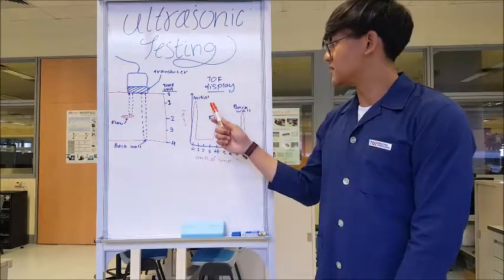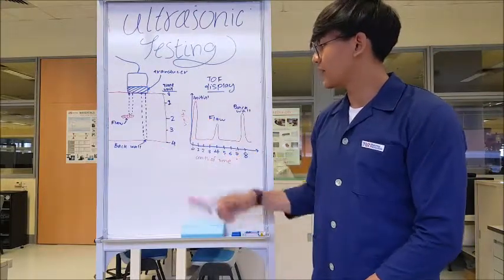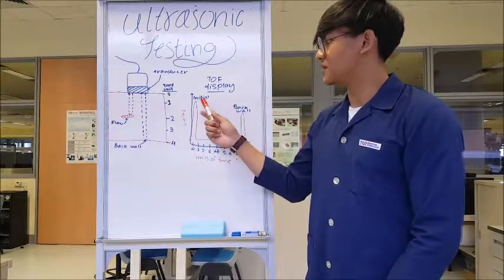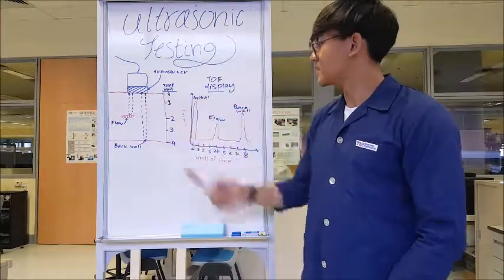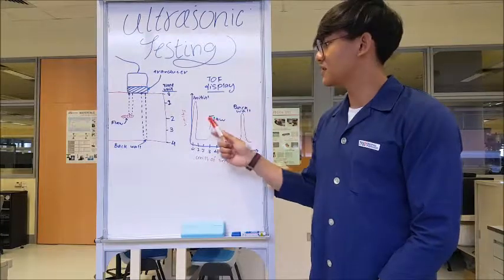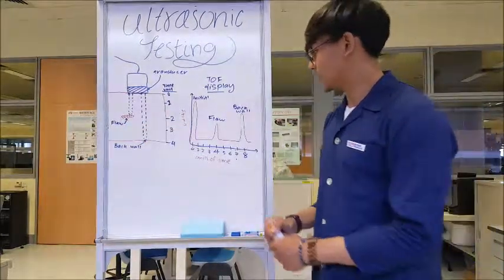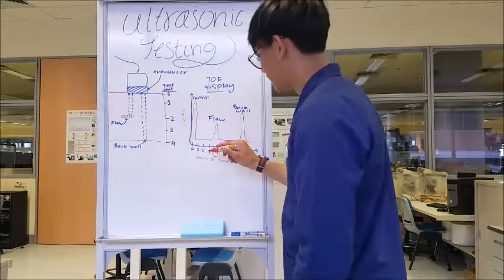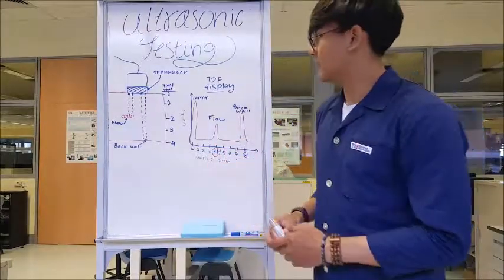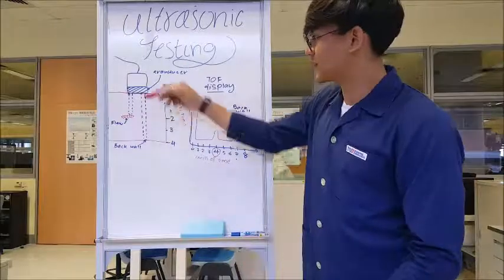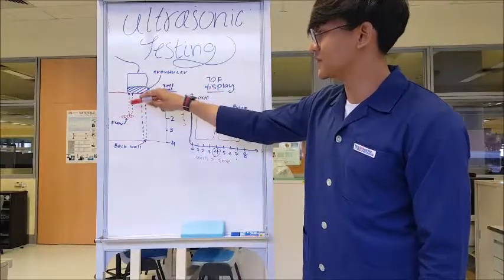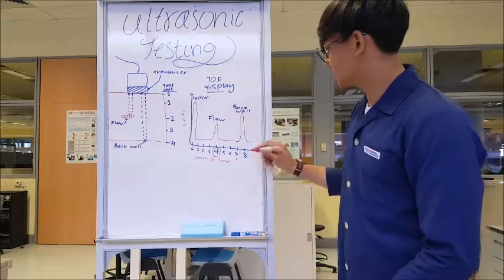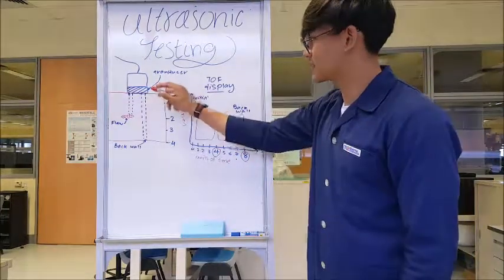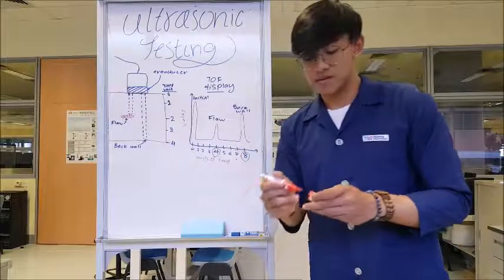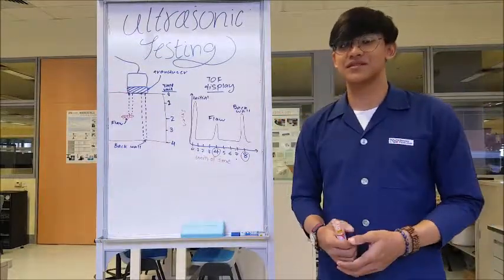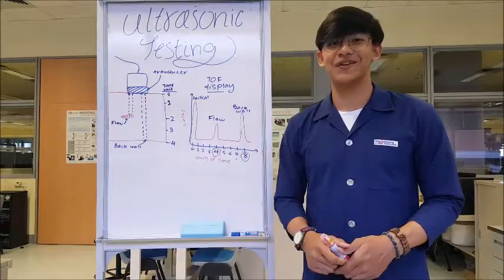So this is the display for this example. There are three phases here. First, the initial pulse from the transducer. The second one, the flaw reflection. The unit of time here is 4, but in reality it's actually 2, but it's 4 because the sound is reflected down and up, so 2, 2. The same goes for the back wall, which is 8, where it goes slightly further down and up. This is an old method, but it's still very useful up to now to detect flaws in a material.